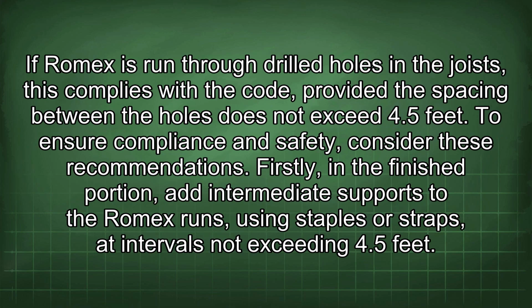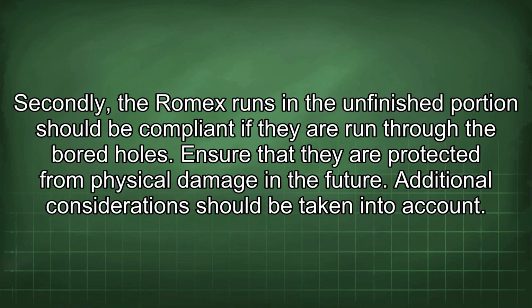If Romex is run through drilled holes in the joists, this complies with the code, provided the spacing between the holes does not exceed 4.5 feet. To ensure compliance and safety, consider these recommendations. Firstly, in the finished portion, add intermediate supports to the Romex runs, using staples or straps at intervals not exceeding 4.5 feet. Secondly, the Romex runs in the unfinished portion should be compliant if they are run through the bored holes. Ensure that they are protected from physical damage in the future.